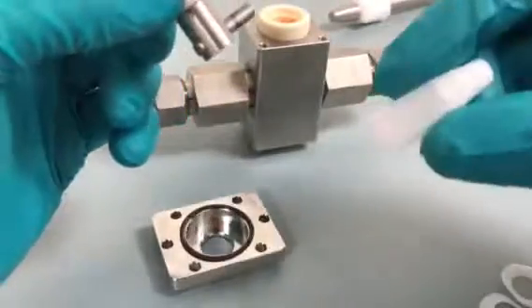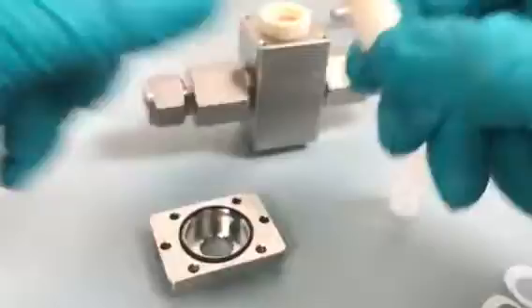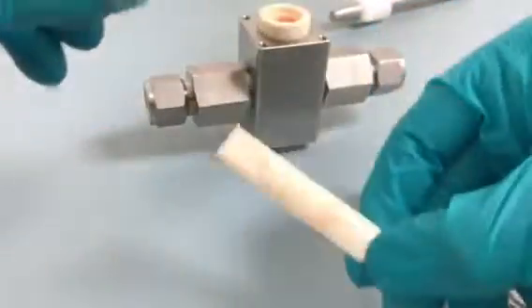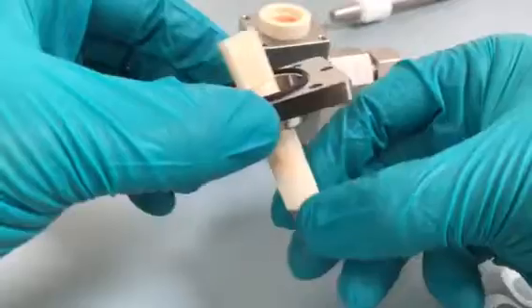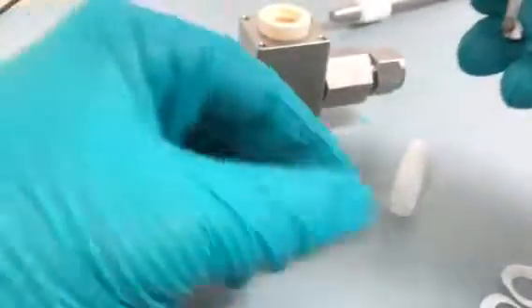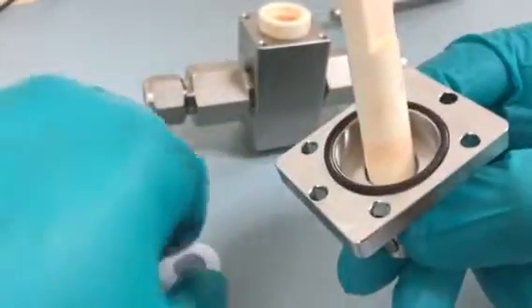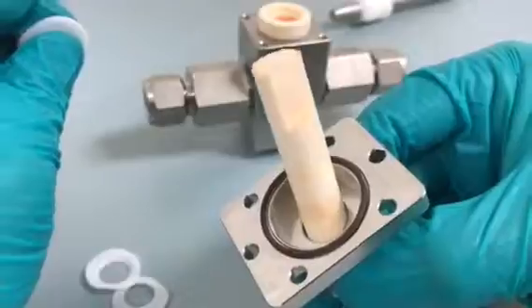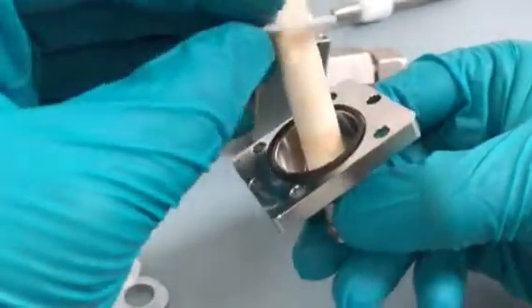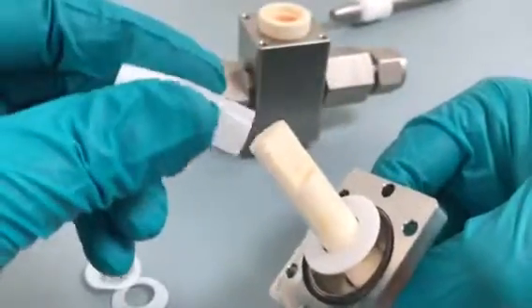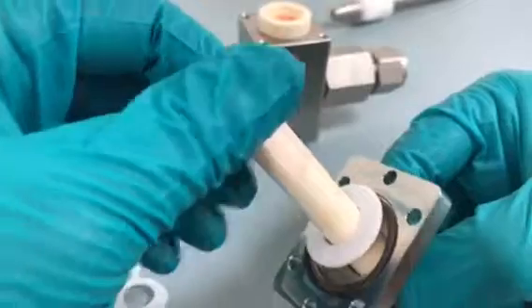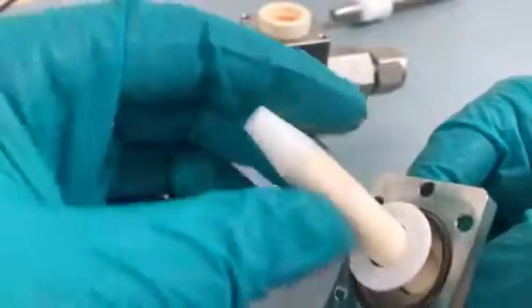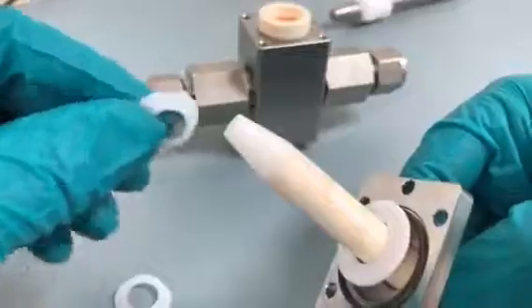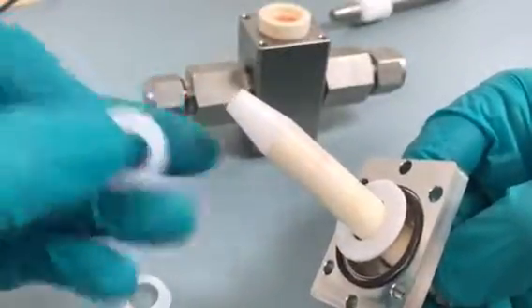We're going to need the lip seal tool at this point, and so we will insert the piston through the pump body, the pump plate. Next, installing the gland washer. Next, utilizing the lip seal tool. The lip seal tool protects the lip seals from the sharp edges of the ceramic.